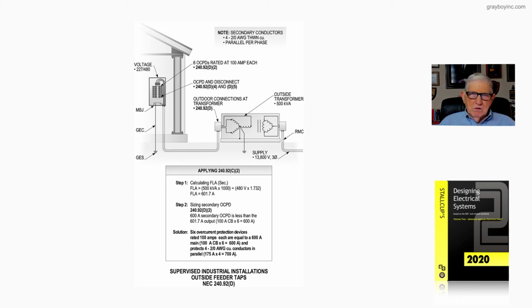Now, in the solution, if we had 6 100 amp mains, that'd be 600 amps. The output of the transformer basically is 602 if you round up, so the output of the transformer is protected. And then 4 2-aught conductors at 700 amps, then our mains have protected, if there's 6 of them, 600 amps, the conductor plus the output of the transformer, or we could have 1 600 amp main that would do the same. So that's what this figure 20-43 is illustrating.